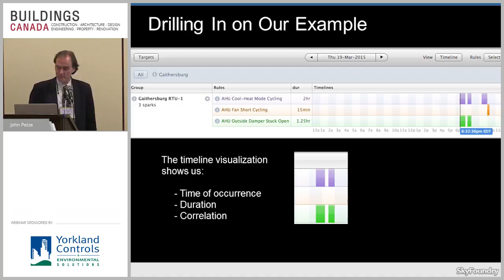But then it does this interesting thing, which is to automatically collect relevant information. You might ask yourself, how would it know what's relevant? This has to do with the fact that when we bring the data in, we tag it, and it creates information that the software can interpret. If the issue happened in a specific site, this happens to be Gaithersburg, Maryland, well, I might as well get the weather and show you the weather when that problem occurred, because that might be helpful to you. And the issue was detected on a specific rooftop unit, so maybe I should get all of the I/O information from that rooftop unit. I should get the discharge pressure, the discharge temp, the return temp, the zone temp, the set point.